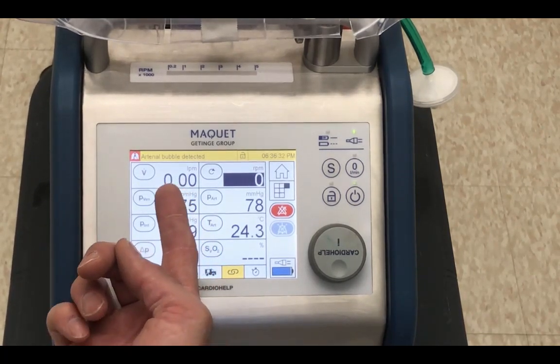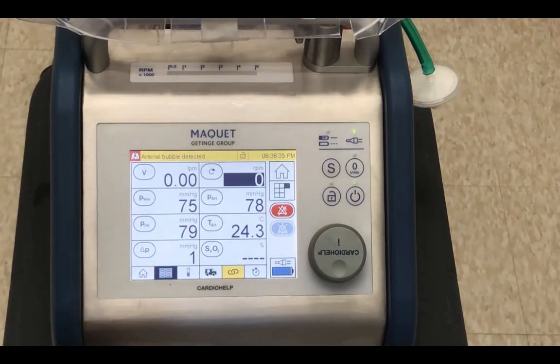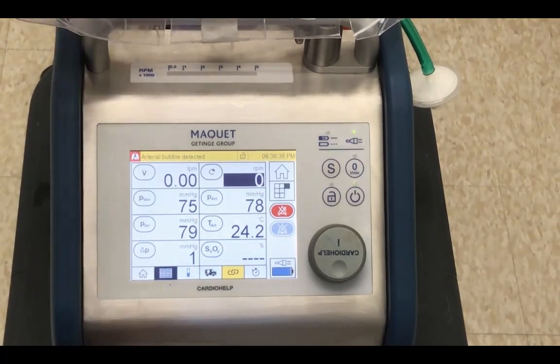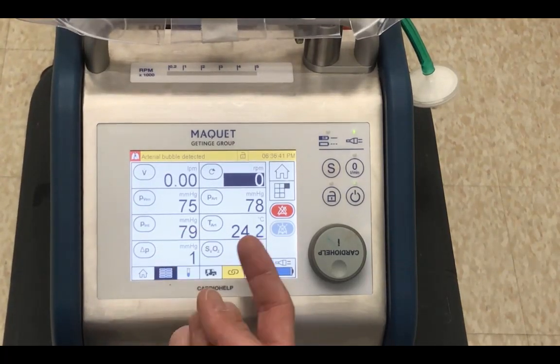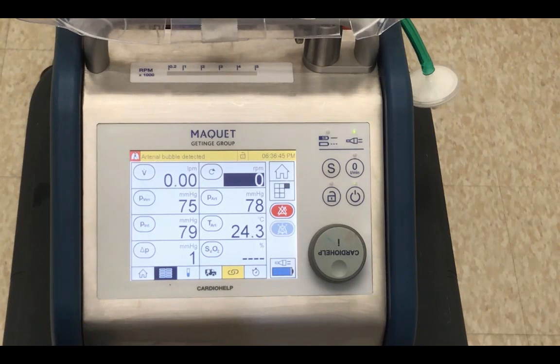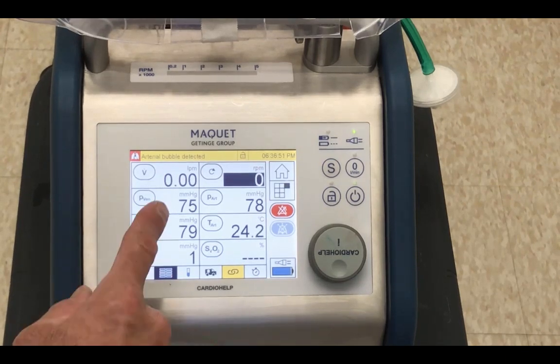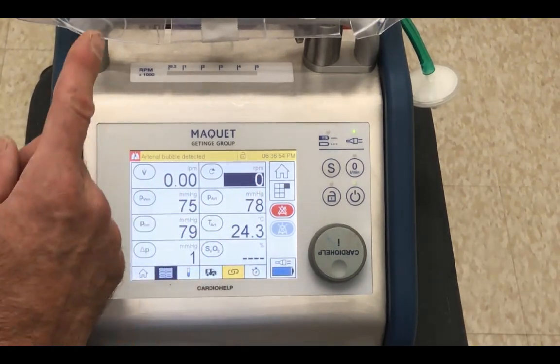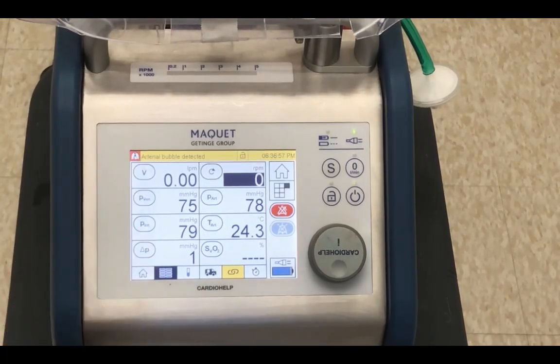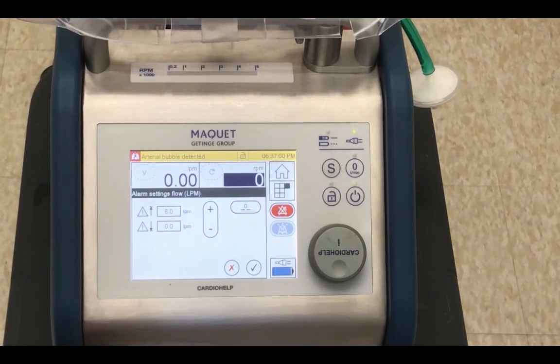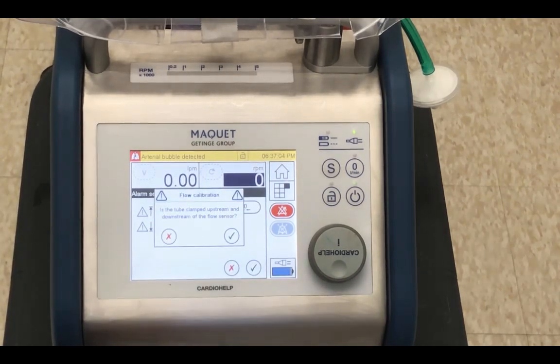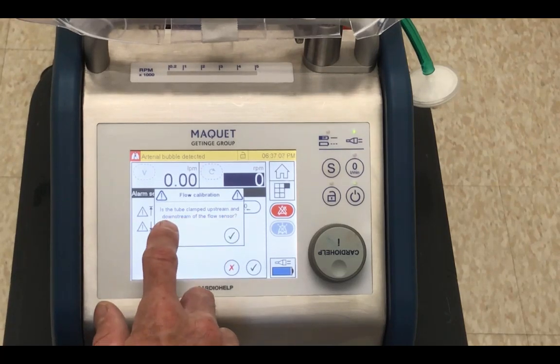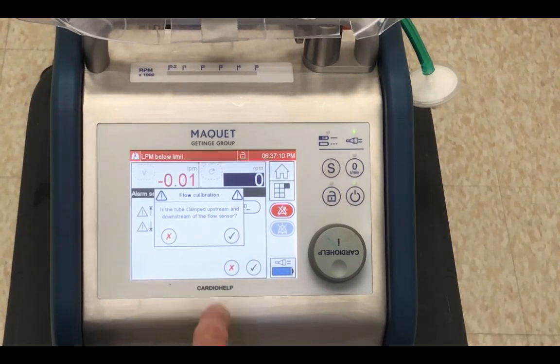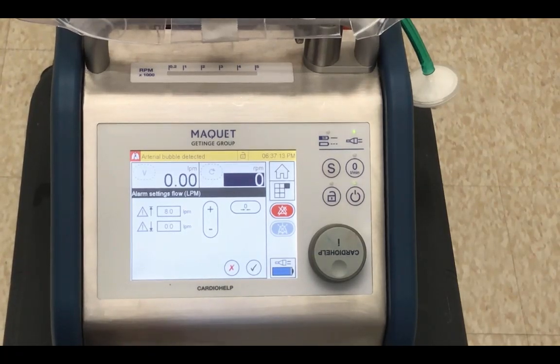So to zero the flow probe, looks like we don't really need to because it's already reading 0. But the method for zeroing the flow probe is after you have fluid in your system, then you place a clamp on the arterial line where there's a piece of tape that shows you that you should place clamps there. It's right next to the flow probe, although the truth is you could put it anywhere. And come over here. While the RPMs are 0 and the flow is 0 and confirmed by a clamp, you can touch the flow. Go into this menu, press the 0, and it asks you, is the tube clamped upstream and downstream of the flow sensor? We've got it upstream. That's good enough. Confirm that is true. And then it just re-zeroed, and you can enter the data.